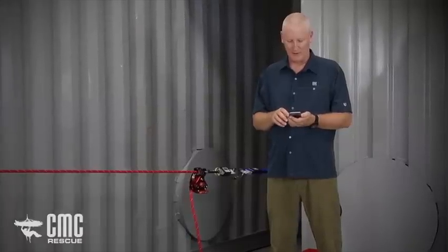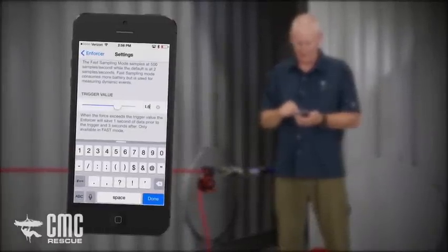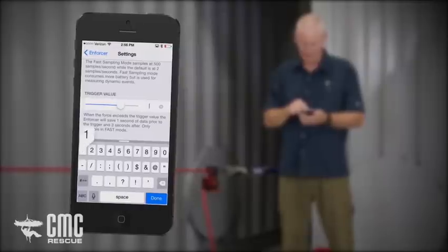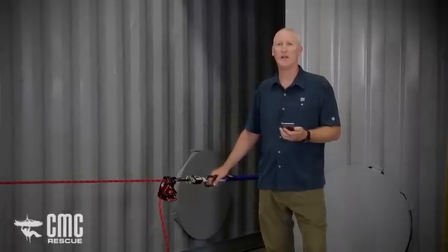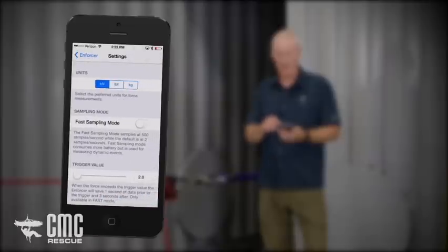To set a specific value for the trigger, tap in the box, enter the number, and click done. Both the Enforcer and the app can display the forces in the system in three different units: kilonewtons, pounds force, or kilograms force. The displays are set independently — on the Enforcer using the force button, and on the app by going to the settings page and choosing a different force for display.